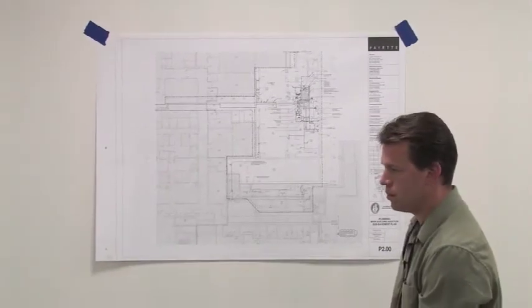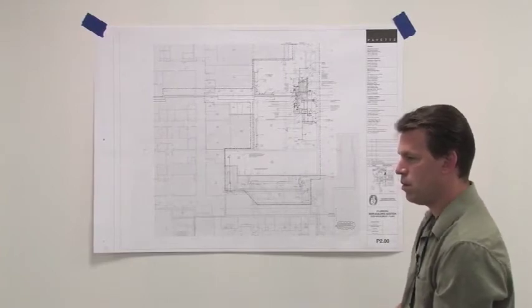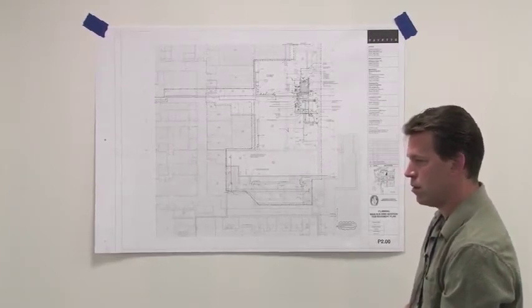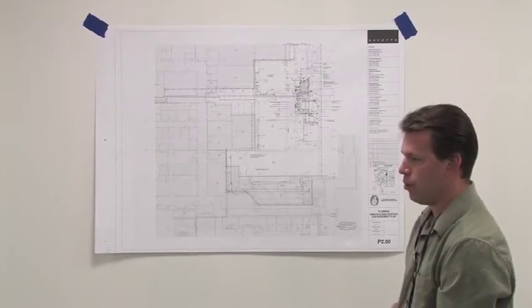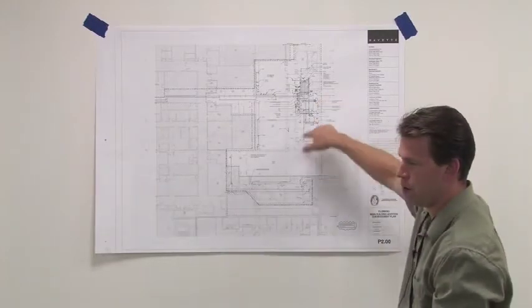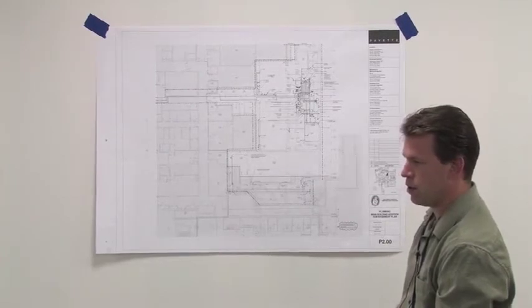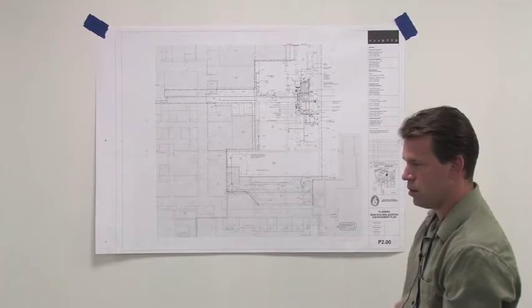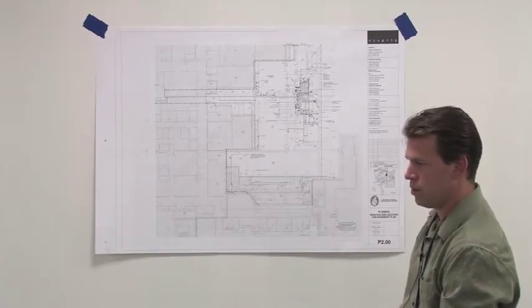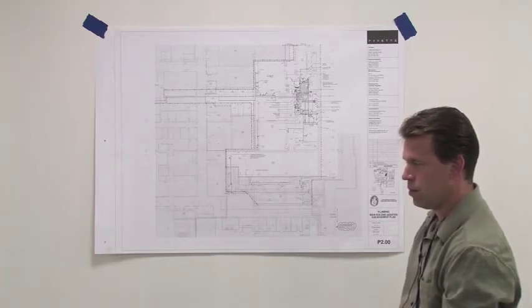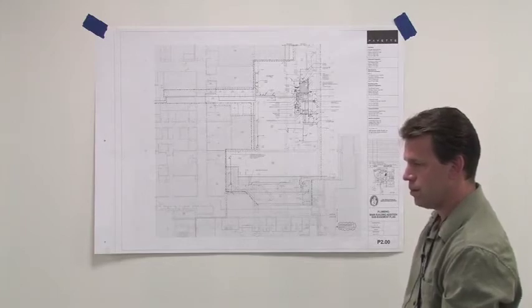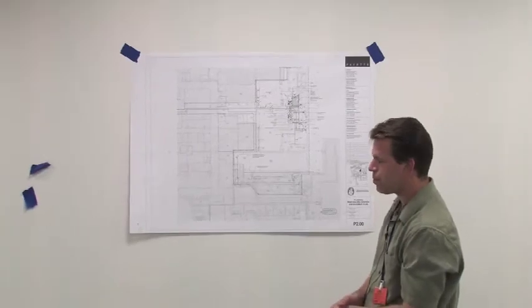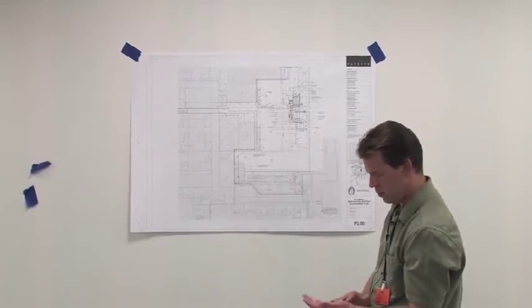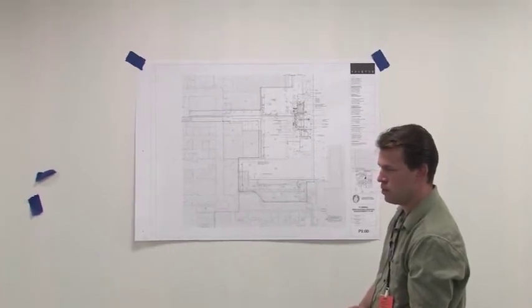Okay. You want to touch base on the chlorine system? Well, before I move on, one second, Kenny. The hot water heater is medium pressure steam, correct? Yes, but it's knocked down to low pressure at the equipment. Just FYI, because we just went to the other training, if you missed that, the HVAC steam comes from the steam tunnel, express high pressure steam up to the fourth floor. It gets pressure reduced at the fourth floor mechanical room, and then the steam from the fourth floor mechanical room goes back down the building and serves that 60-pound hot water heater, where it gets reduced again. It's good information to know. It's coming from the fourth floor pressure reduction station, the only station in the whole building. High pressure comes in from the tunnel, goes right up to 4, distributes from 4, and then goes down and up.